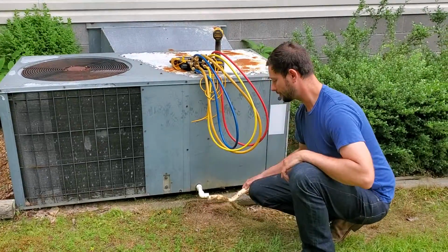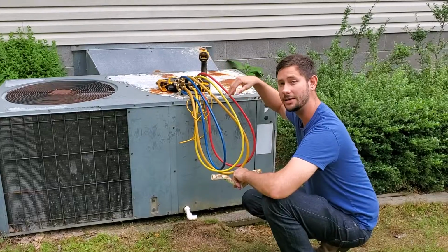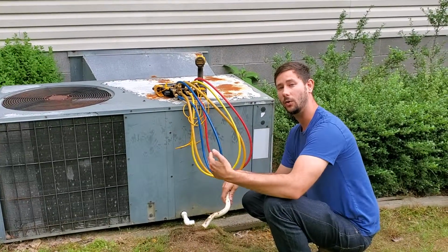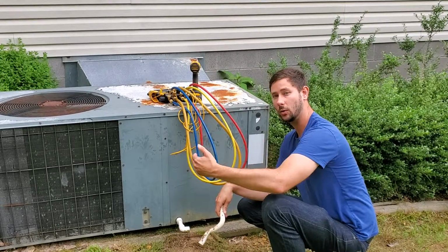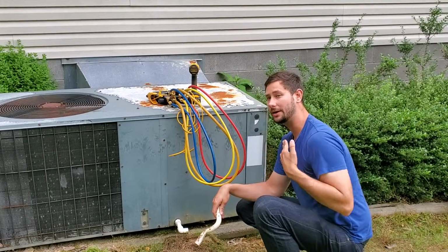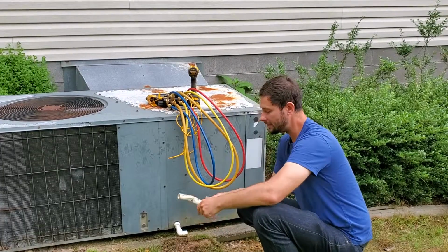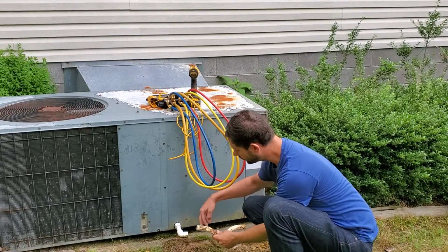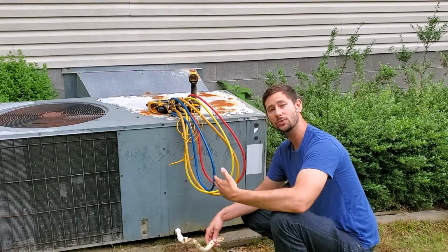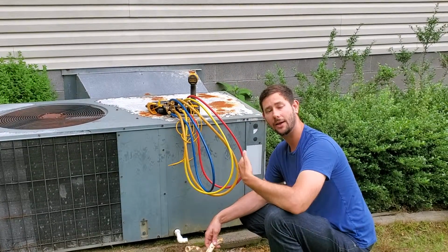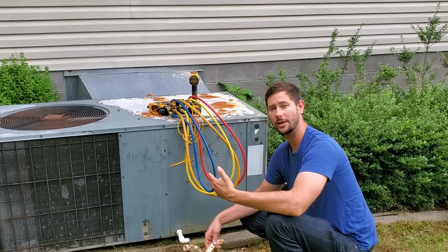If you don't know what the purpose is, when your coil is on the negative side of the airflow, that means that your fan is in front of that coil and it has to pull the air from the return in the house past the coil and then into the blower, and then it pushes down the supply. When it's on the negative side, that means that it pulls the water back through this drain. And if it does, that means that the water will stay in the pan and it'll circulate in the house, causing higher humidity conditions. And we don't want that. We want all the water to drain out efficiently.